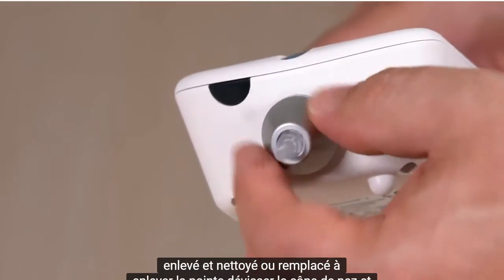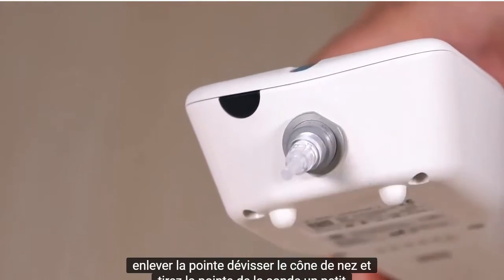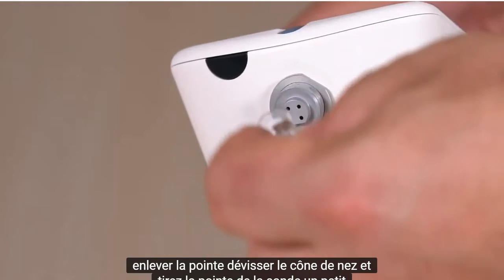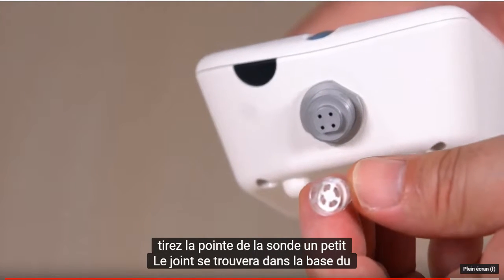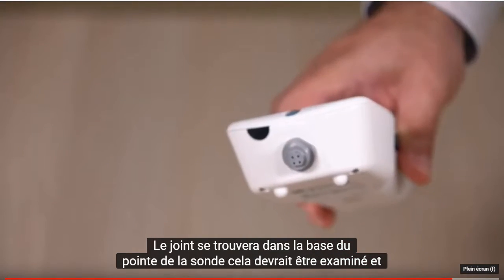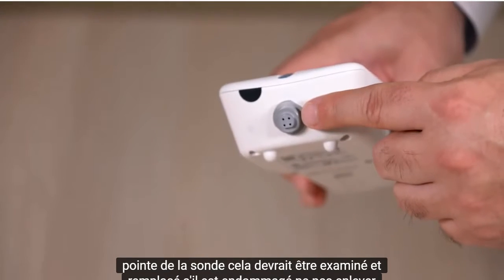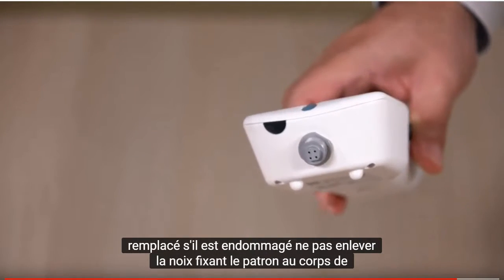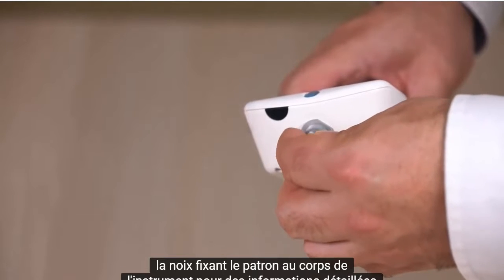To remove the tip, unscrew the nose cone and pull the tip off the probe boss. A small gasket will be found in the base of the probe tip. This should be examined and replaced if it is damaged. Do not remove the nut securing the boss to the body of the instrument.